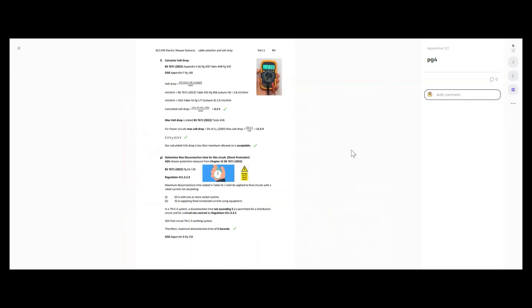This gets us thinking about grouping as well — it's often we're just seeing the number of cables in a bit of trunking or containment and we add them up and jump to the tables when, really, are they all under load for the required time? Are they needing to be part of that calculation? If not, don't put them in there. So 16mm — we're happy with that. We've selected the cable based upon the design current and any correction factors and the way it's been installed. We're okay with 16mm twin, not a problem.